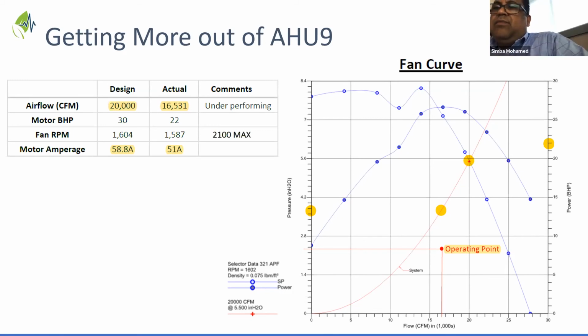Well, we'd have to investigate where the leakage is, and if there's any buildup of debris on the blower motor or the blower, to see what's going on in the unit itself. You mean we're off the curve, like the static pressure based on where we are with horsepower and so forth. We're well below the number.